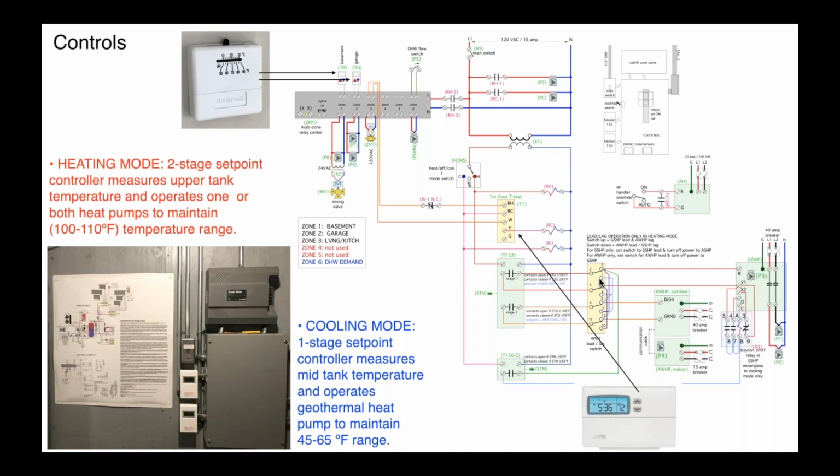This way, when you put that switch in the cabinet, instead of trying to work your hands in that cabinet and attach to terminal number 7 with a tiny little screwdriver in an awkward position, you can simply wire nut or use a compression connector to that pigtail. It just makes it go a lot easier, and it's also easier to trace that wiring if you're trying to troubleshoot it. All your pigtails are numbered corresponding to the switch.